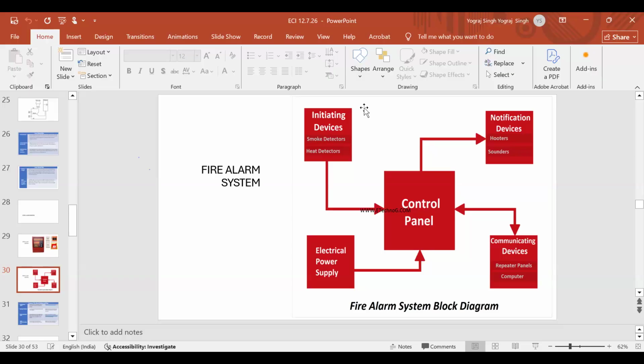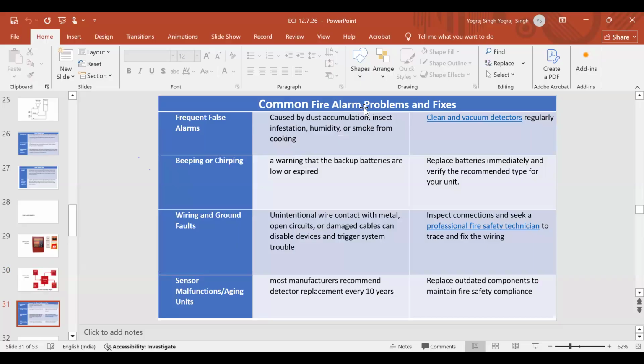Now, there are some communicating devices. What happens? Suppose there is a fire in a building. The first thing is, an outsider who is coming to fight the fire should know where the fire is. Where the fire is will be known by the repeater panel. So if I go back, this is the old system where each circuit was reflected by an LED. So this will tell you where my fire is.